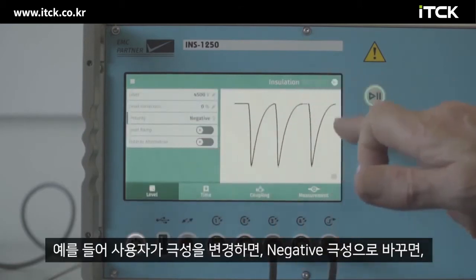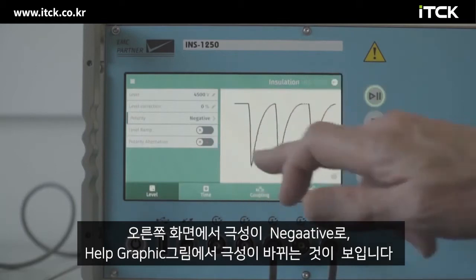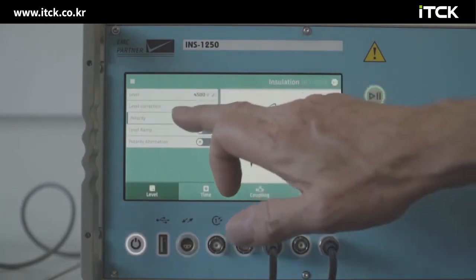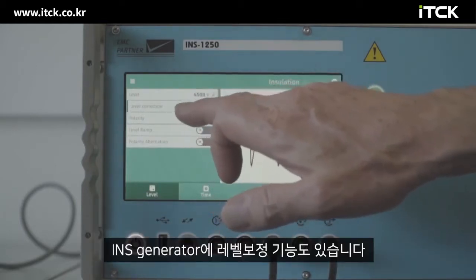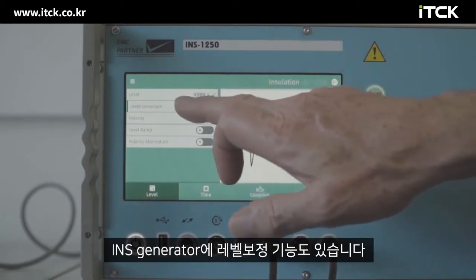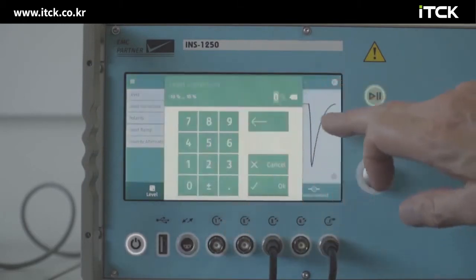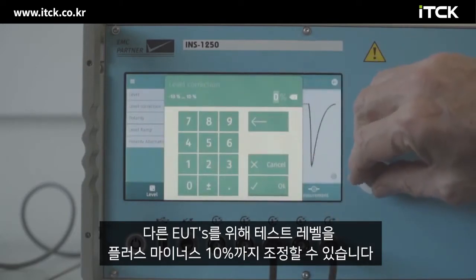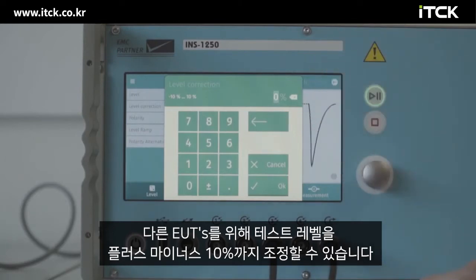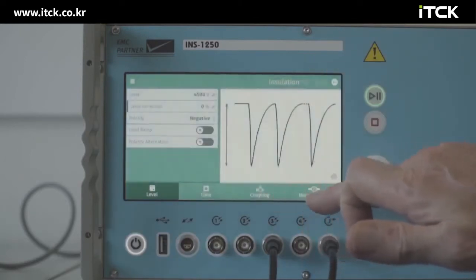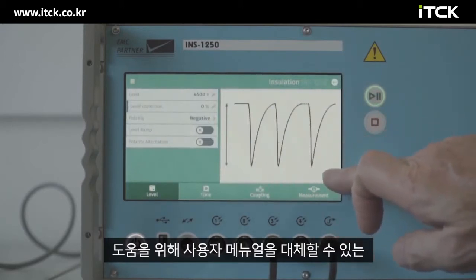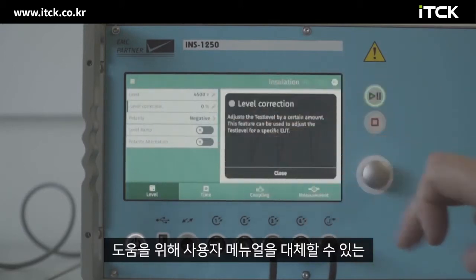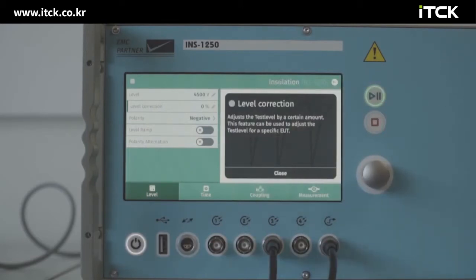So for example, we change polarity, we see the negative polarity will occur. Level correction is a feature we have in the INS generator, where we can adjust the test level up to plus minus 10% for different EUTs. In terms of the help, we have also an online help integrated into the generator, which replaces in some part user manuals.